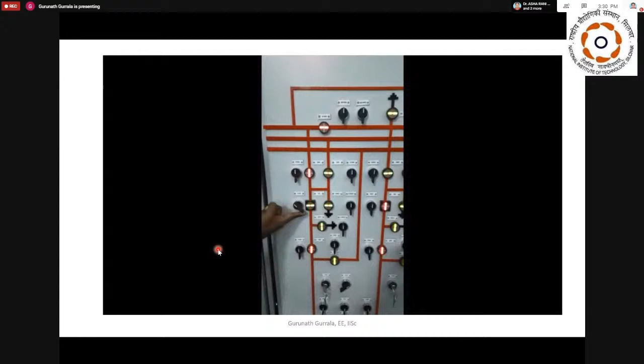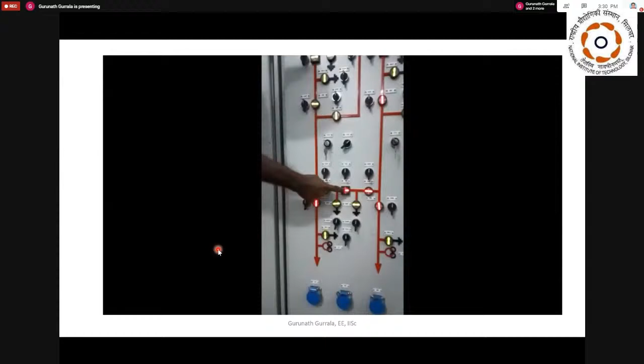I will switch this off. Now if this isolator is on, this will also not be able to turn on. Now it will go off - this is interlocked with these two isolators. Similarly, for this isolator, these two circuit breakers must be off.